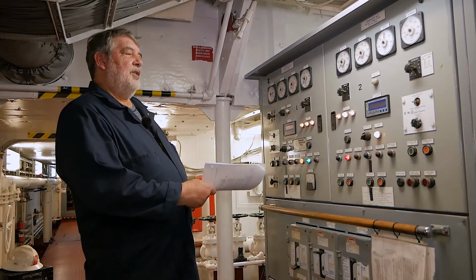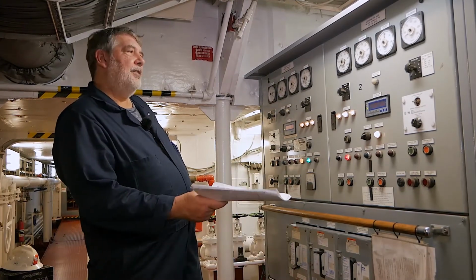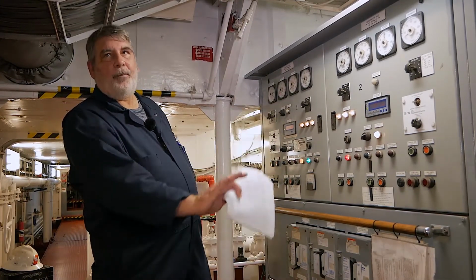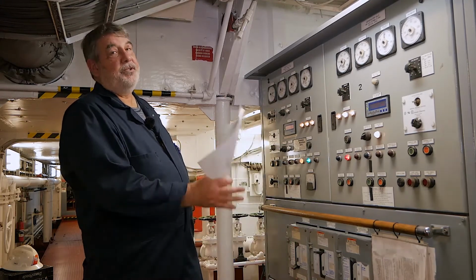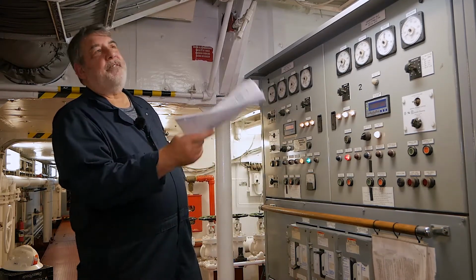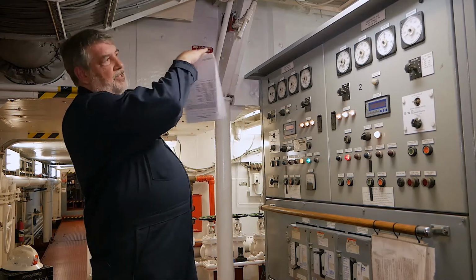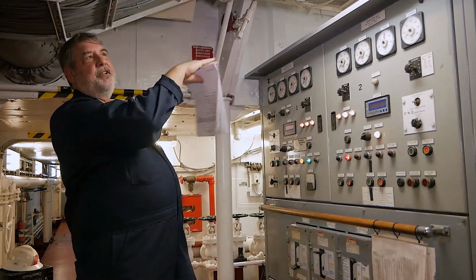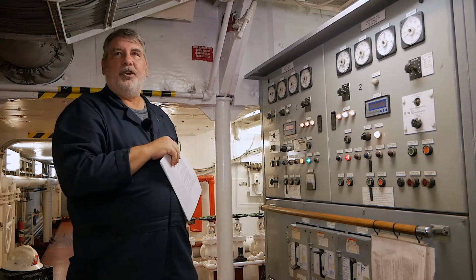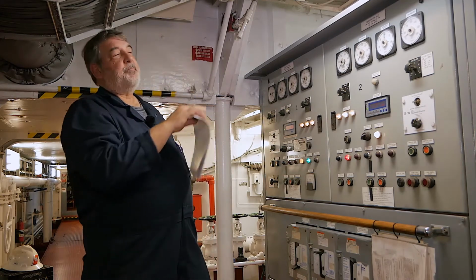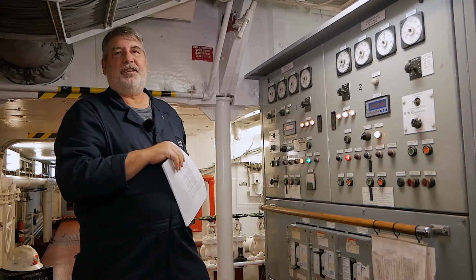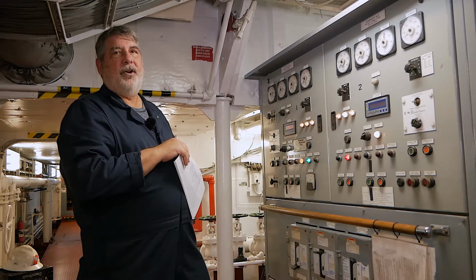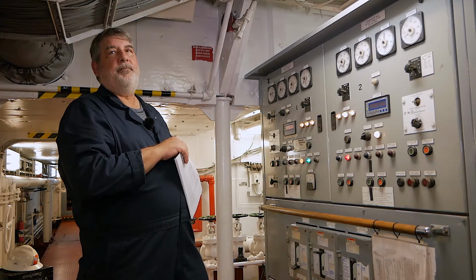Okay, last tips are to always look for openings in the switchboard and make sure those get closed, and verify the cleanliness of the top of the switchboard. In machinery spaces, dust and oil tend to accumulate up there, and especially if any cable penetrations go down into the top of a switchboard, you have to be up there and put eyes on it.